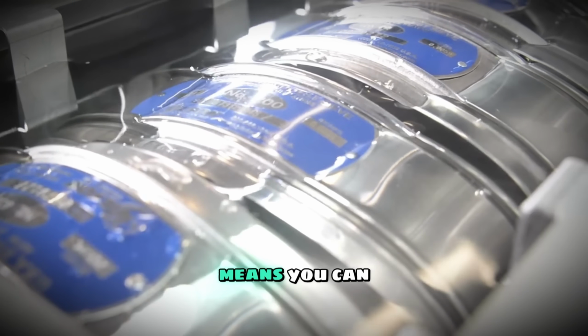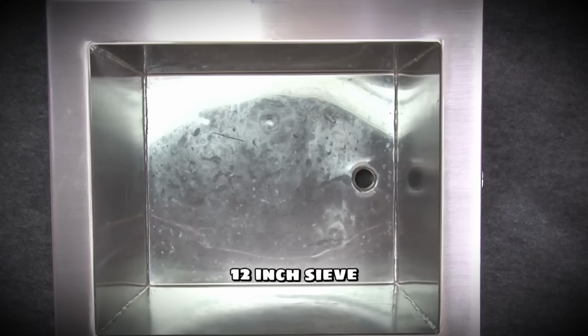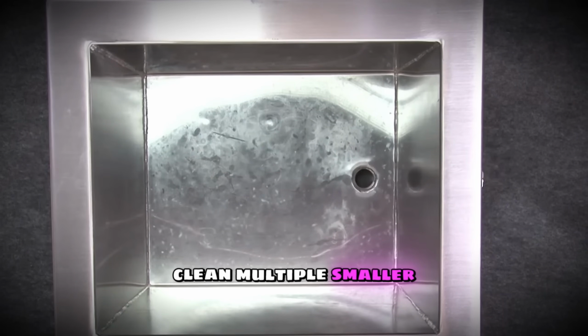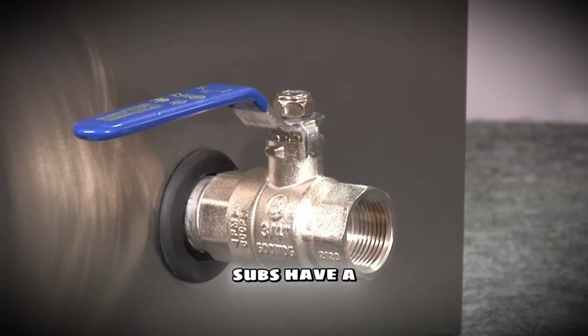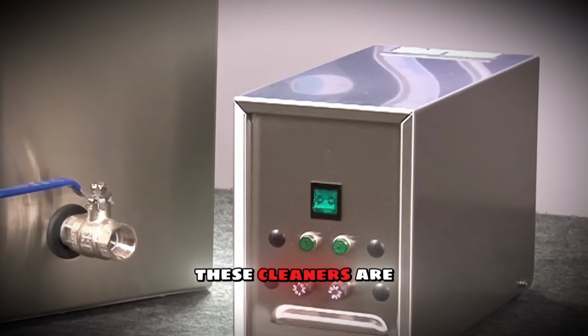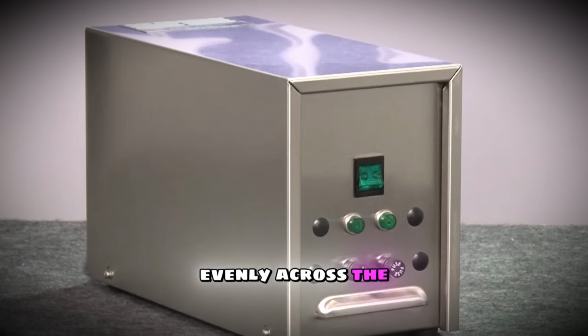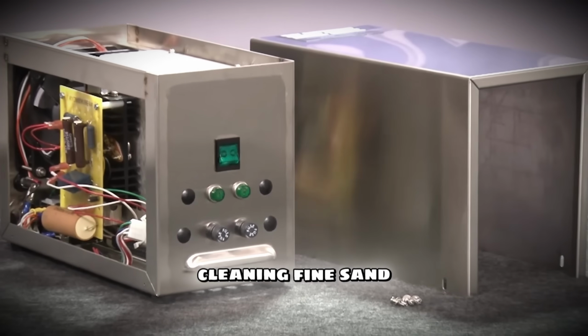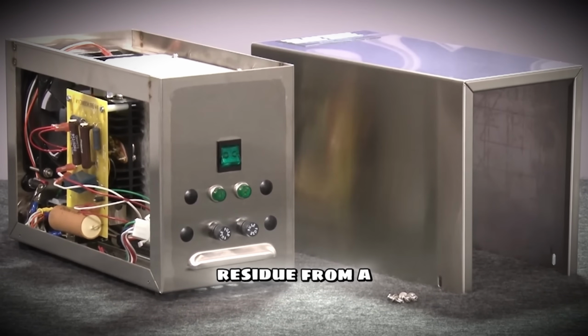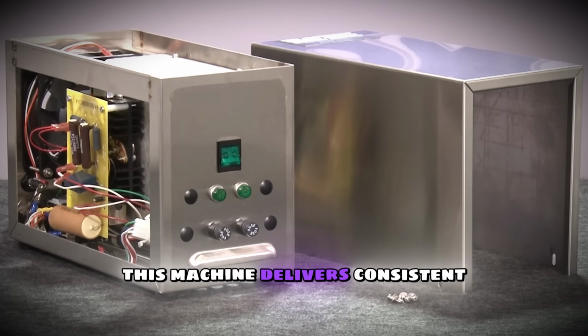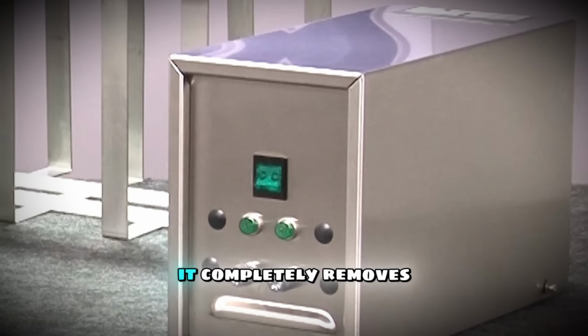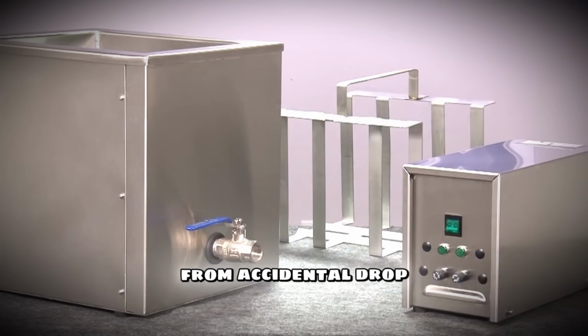The larger footprint means you can easily submerge a massive 12-inch sieve, or in some configurations, clean multiple smaller sieves simultaneously. Because 12-inch sieves have a much larger surface area and often hold heavier, more stubborn aggregate materials, these cleaners are equipped with heavy-duty industrial transducers. They distribute the ultrasonic waves evenly across the entire expanse of the larger tank, ensuring there are no dead zones. Whether you are cleaning fine sand from an 8-inch sieve or coarse gravel residue from a 12-inch sieve, this machine delivers consistent, repeatable cleaning power. It completely removes the manual labor equation from your lab, protecting your staff from fatigue and your equipment from accidental drop damage during hand washing.